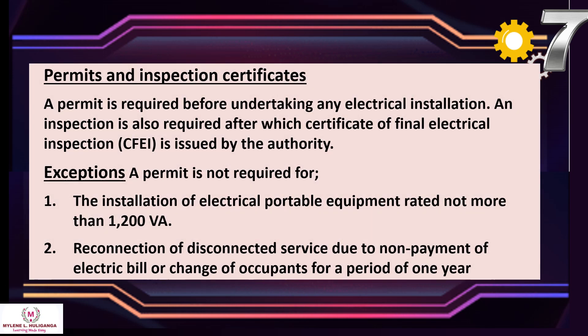Permits and inspection certificates: a permit is required before undertaking any electrical installation. An inspection is also required, after which a Certificate of Final Electrical Inspection (CFEI) is issued by the authority. Exceptions: a permit is not required for the installation of electrical portable equipment rated not more than 1,200 volt-amperes, reconnection of disconnected service due to non-payment of electric bill, or change of occupants for a period of one year.